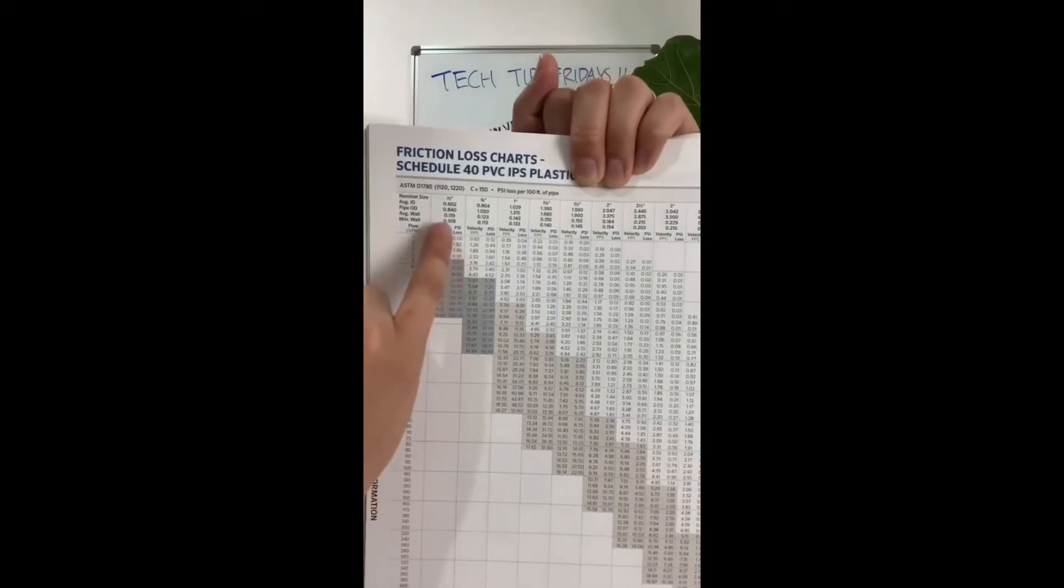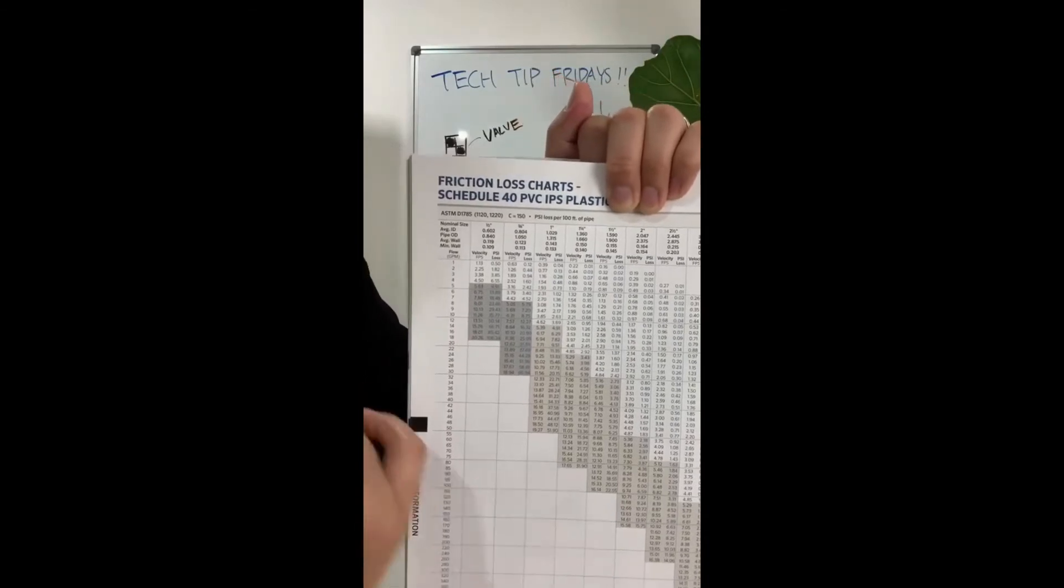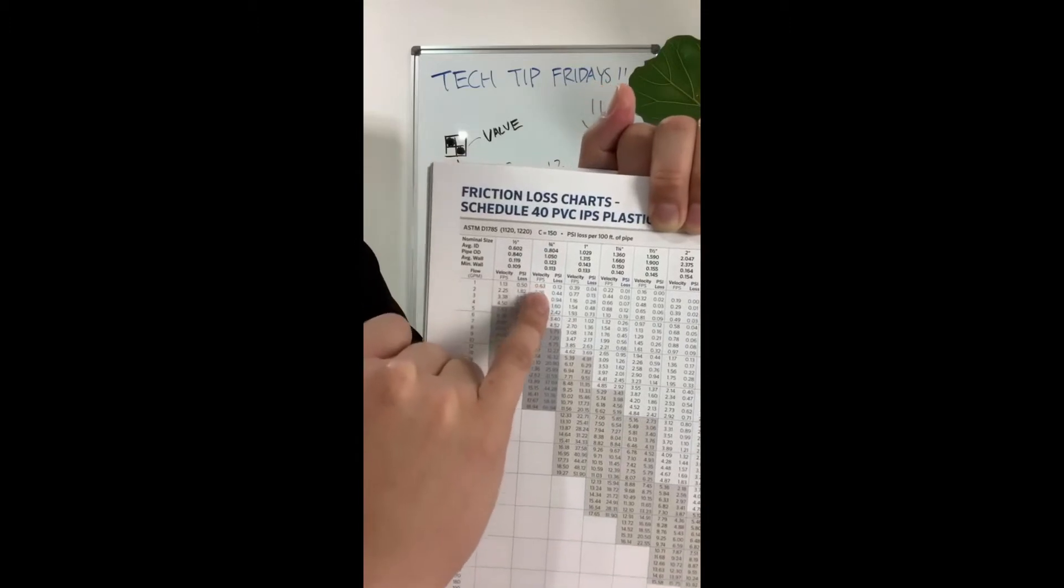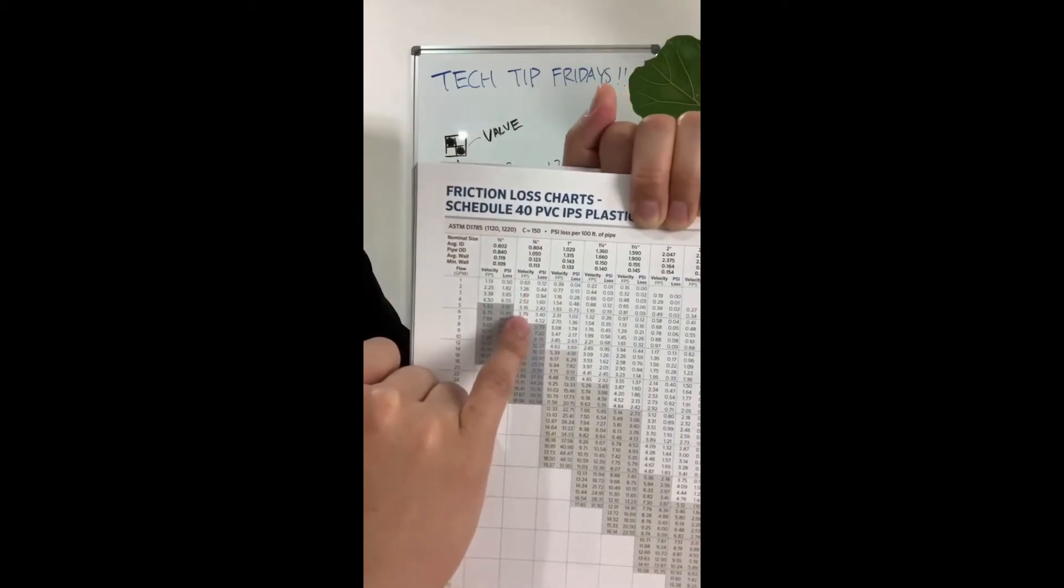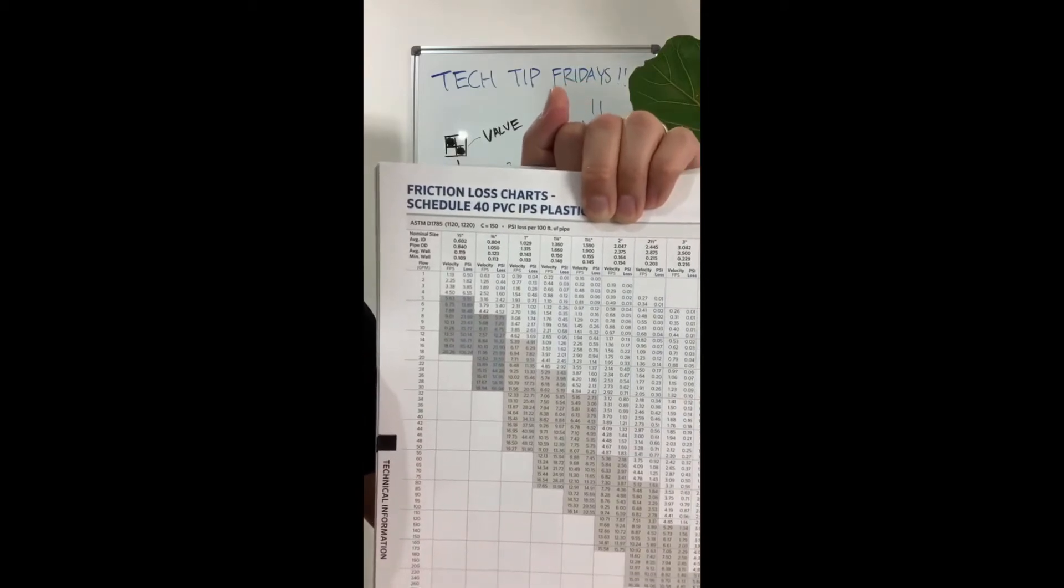Now if you scroll across your 3 quarter inch pipe, when we create our little cheat sheet located on the board, you'll see that 3 quarter inch pipe can go from 1 to 6 GPMs. Notice I didn't go to 7 because we don't ever want to max out our system.